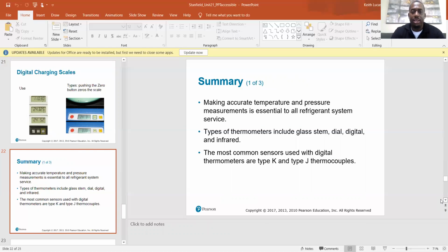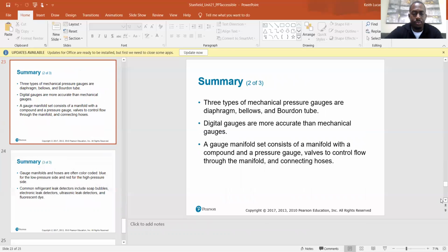So in summary, making accurate temperature and pressure measurements is essential to all refrigerant system service. Types of thermometers include glass stem, dial, digital, and infrared, which is the laser kind. The most common sensors used with digital thermometers are type K and type J thermocouples. 3 types of mechanical pressure gauges are diaphragm, bellows, and Bourdon tube. Digital gauges are more accurate than mechanical gauges. A gauge manifold set consists of a manifold with a compound and a pressure gauge, valve to control flow through the manifold, and connecting hoses.